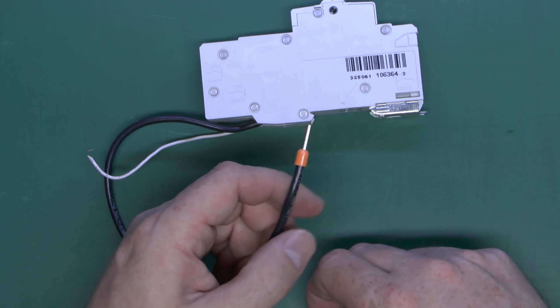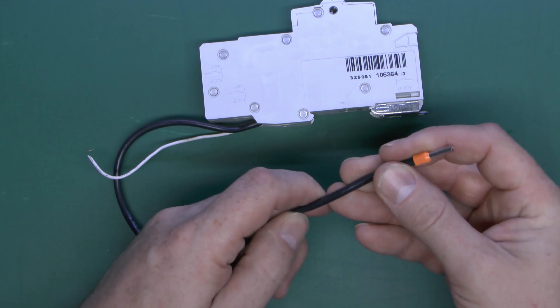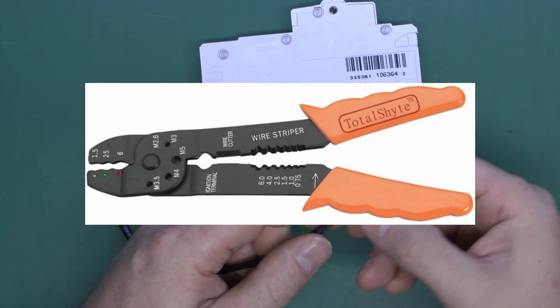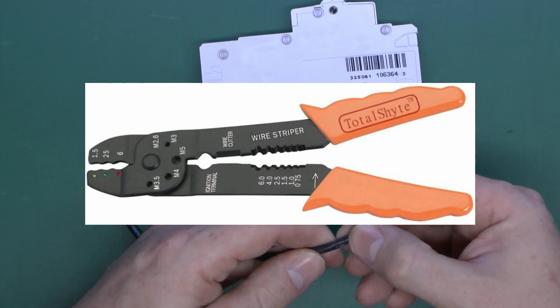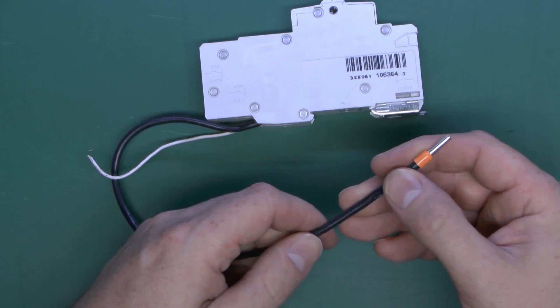Now there are several types of crimping tool available. The cheapo-matic variety, which I don't have here but here's a picture of one, pretty much those are hopeless. And the problem with those is there's no way of controlling the amount of force that's applied. They're literally press and hope. So maybe you applied enough force or maybe you didn't.